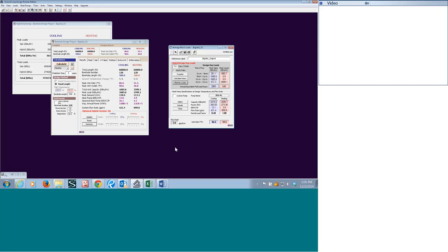And our thermal conductivity values, based on the average TC test for the horizontal bore and trenched loop, and the point TC testing using the handheld meter, they were within 5% of each other. So we were pretty impressed with that, and we've repeated that test on other jobs. And so if cost is an issue and time is an issue on a horizontal ground loop, you might want to consider a handheld TC test meter. Okay. The other thing I like about that, it gives you an actual measured diffusivity instead of an estimated or theoretical diffusivity as per an average TC test.